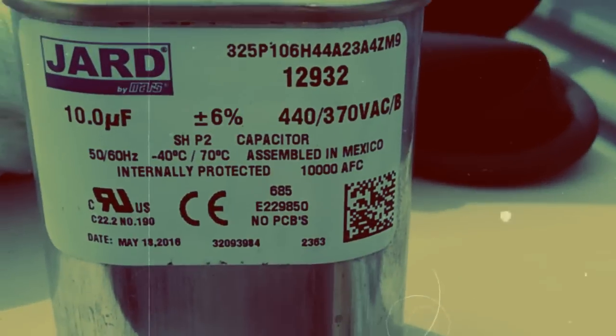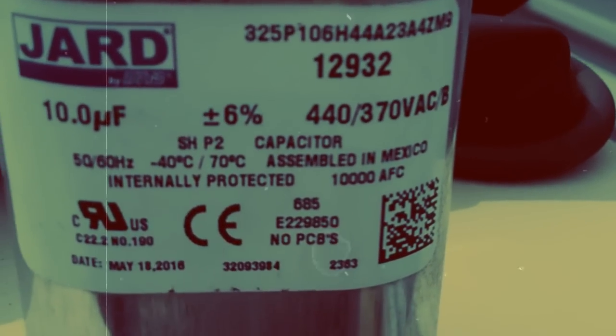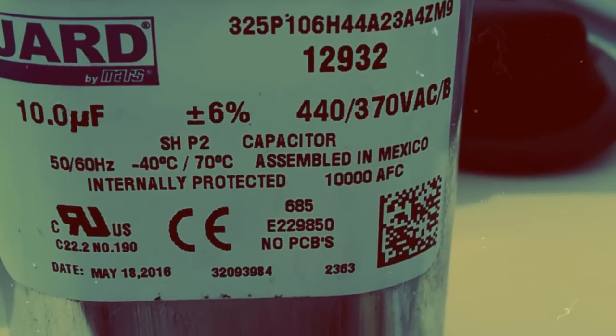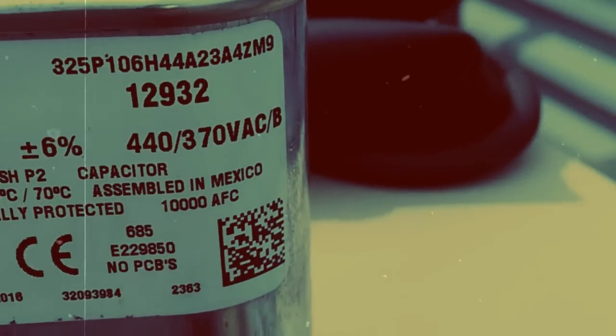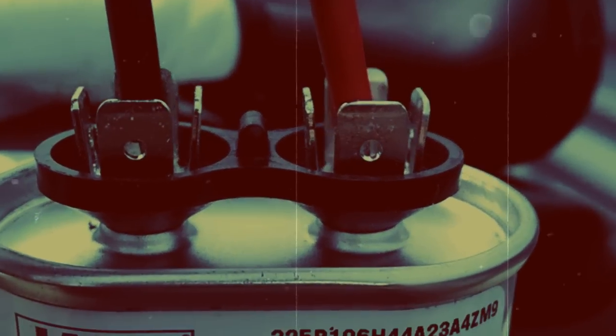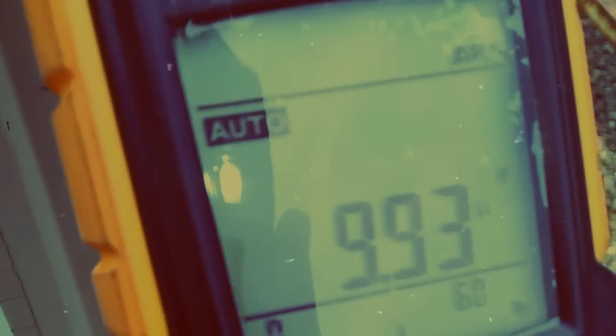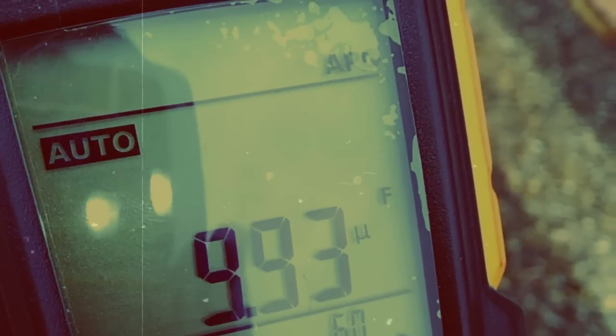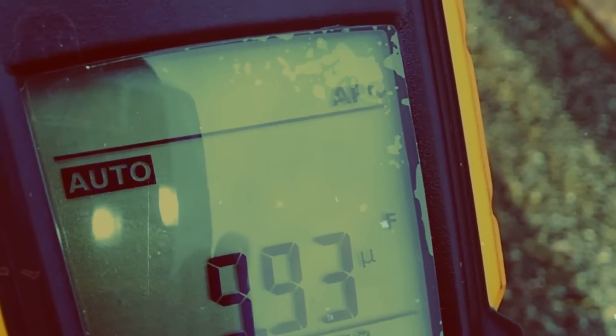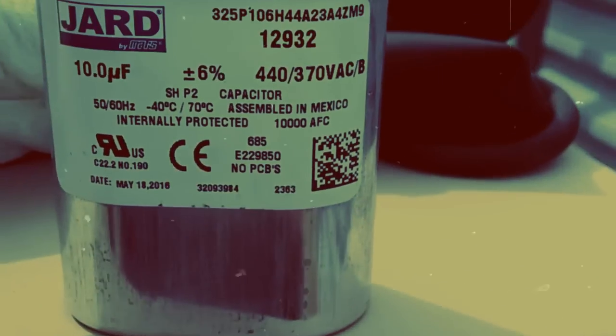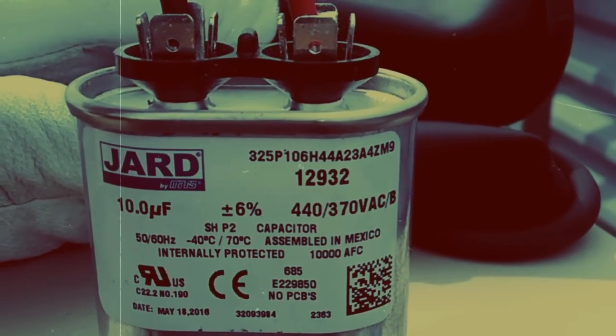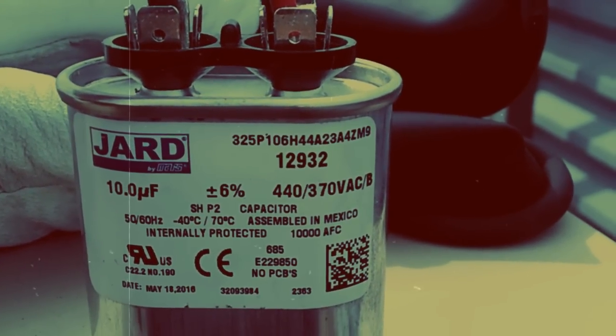Grab our meter leads, we have a 10 microfarad capacitor at 440 volts. And we stick that on there nice and firm. And there we go, 9.93 microfarads. So we know it reads correctly, with the capacitor outside of the system, sitting on top of the rooftop. Let's check it when it's all wired up.